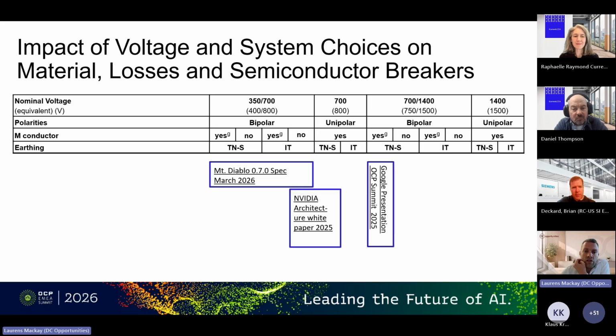And then we have the 750/1500 volt midpoint grounded, TNS grounded system that has been presented by Google at the OCP Summit last October. And then, to put it in perspective, you have the bipolar TNS systems and the unipolar TNS systems that have been covered a lot in current OS — one with the M conductor, and a second system, the bipolar without M, that has been used in ODCA so far a lot, including the IT variant when islanding.